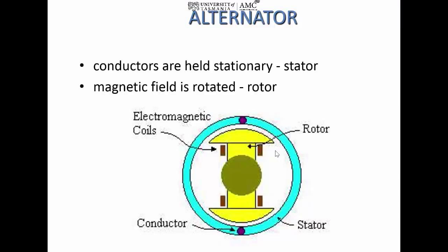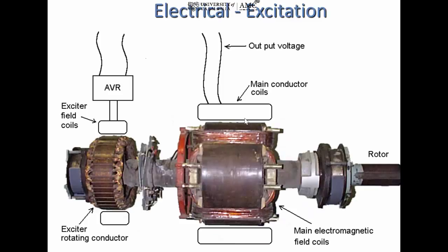So the electromagnets, or the electromagnetic field coils or field poles, are on the rotor. Here we have four electromagnets or four field coils, and these are north-south, north-south. They're two pairs of poles or four poles. There's a four-pole alternator, and then in the stator, or the stationary part, is our conductor or conductors. And here we can see the start of one conductor and the finish of one conductor.